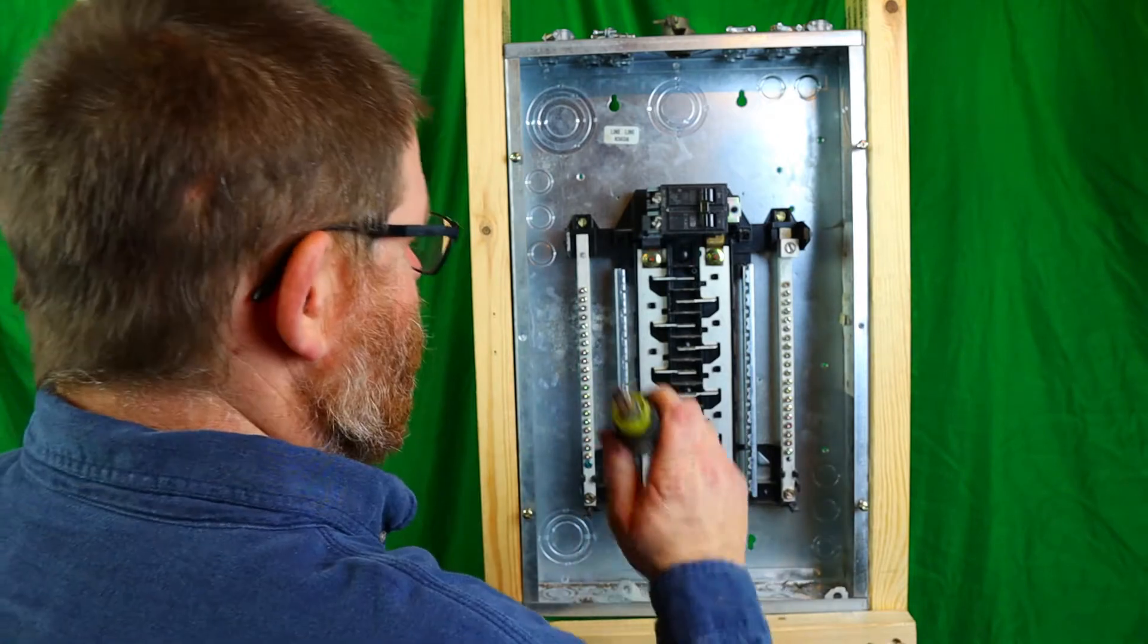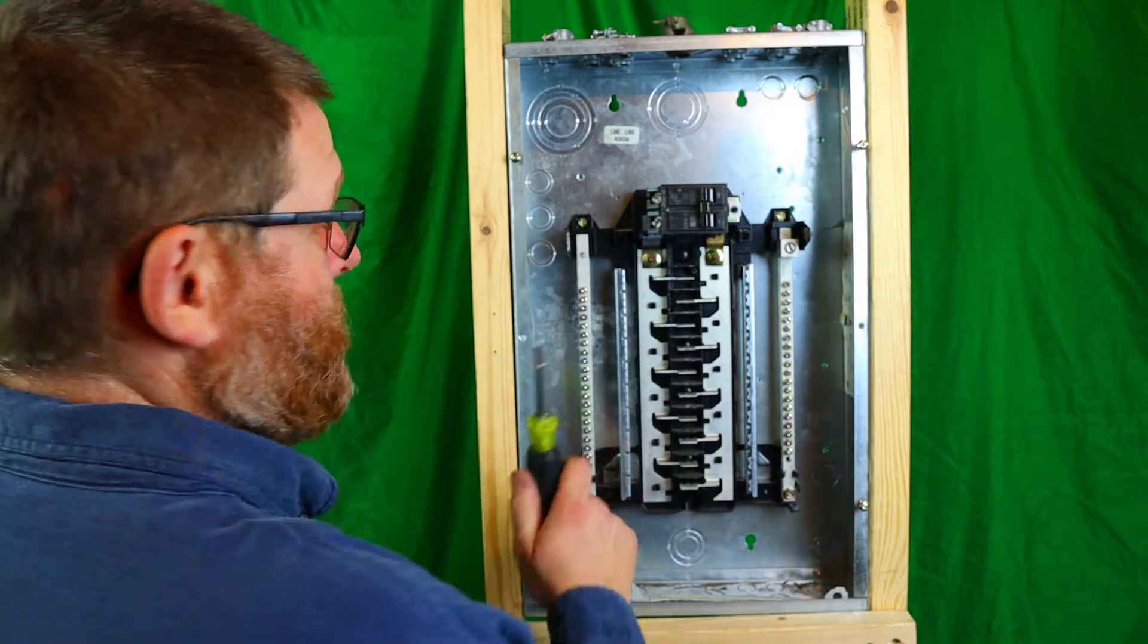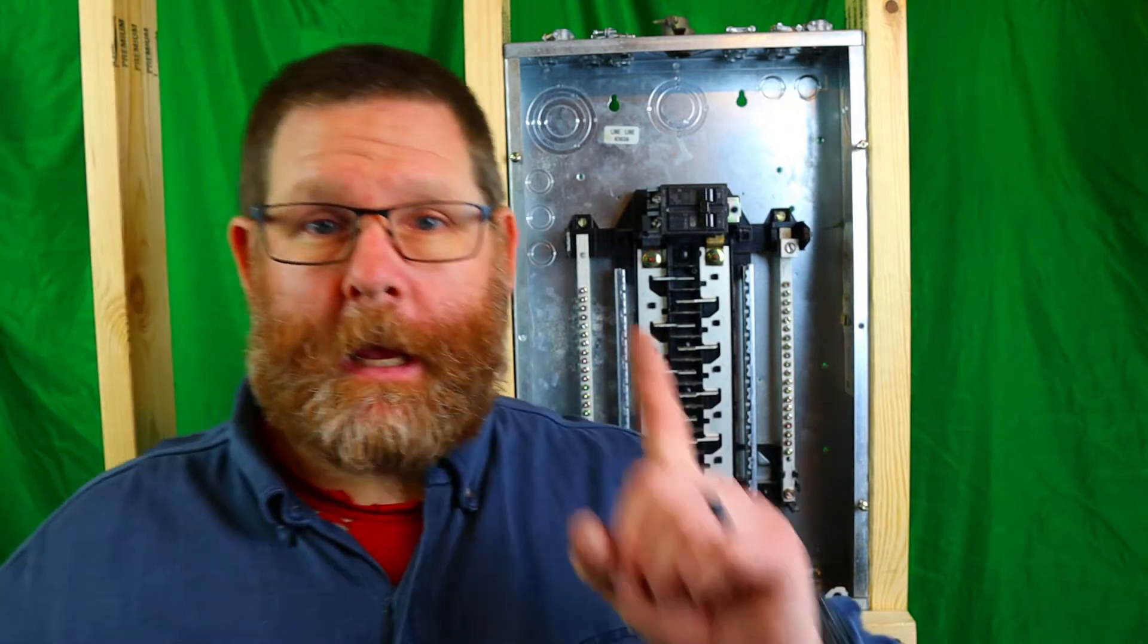But that has to be this way - it has to only be bonded in one spot, and that is your main panel. Or if you have a disconnect, that is where it is bonded.